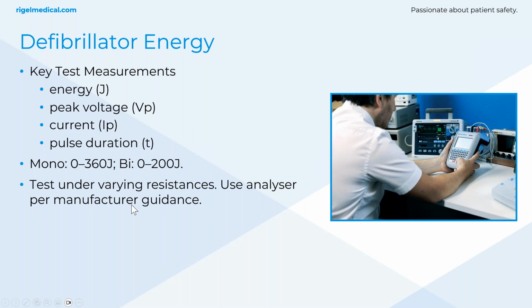Now, you always use an analyzer per manufacturer's guidance. Every model manufacturer will have its own test limits or tolerances that are recommended. It will have different test points, so it varies between models what the test points are. So you always need to refer to the PM procedure of the manufacturer. That's the ultimate guidance you have to follow. But it is on us to try and push the requirements for testing for AEDs, because many of them, as I said, just have self-tests that are specified.